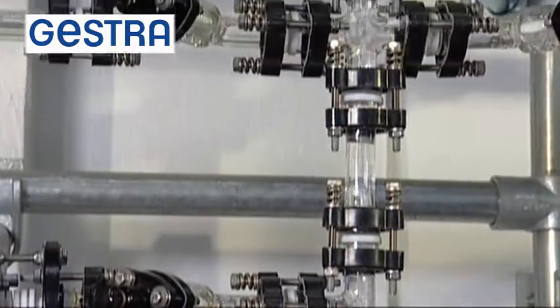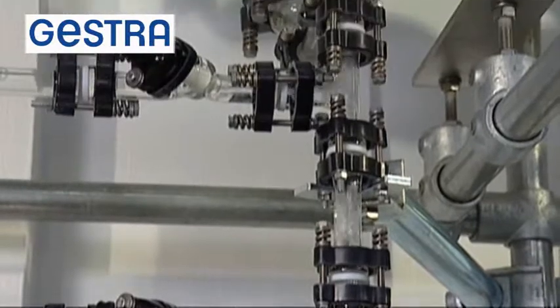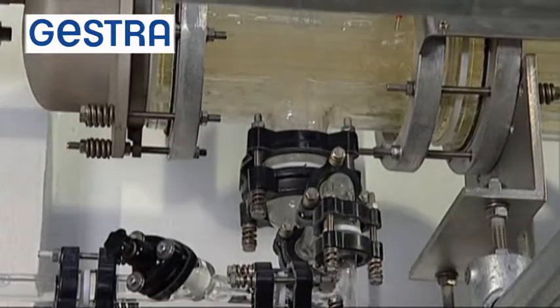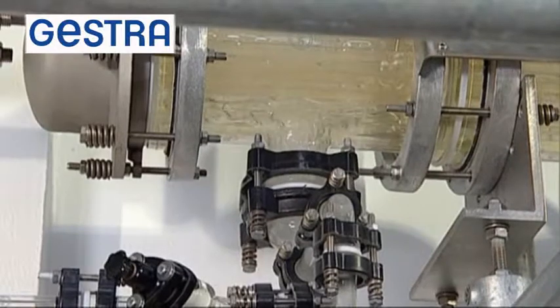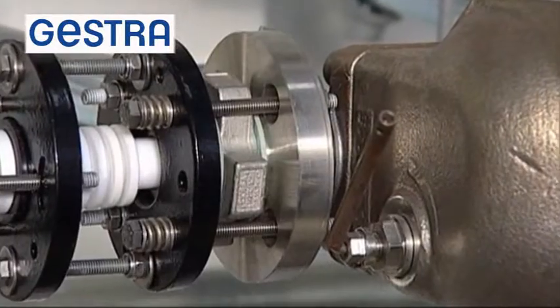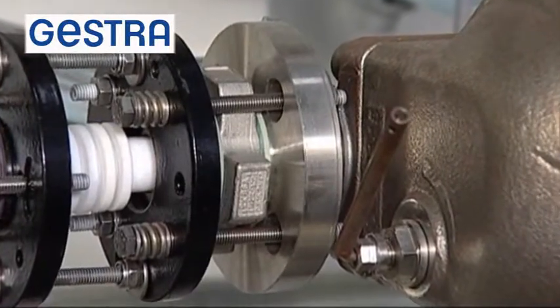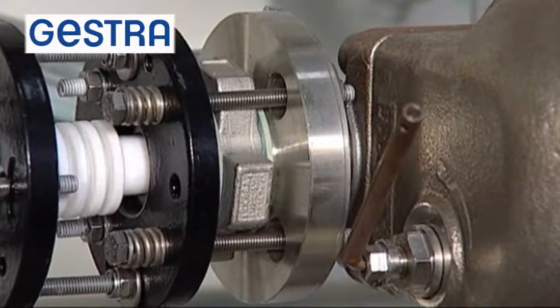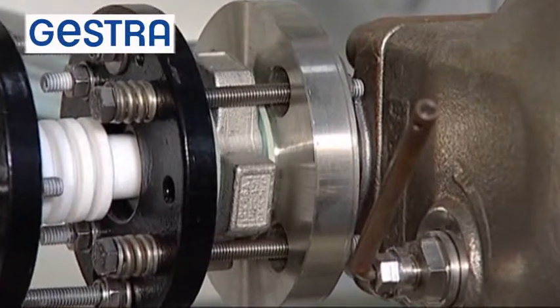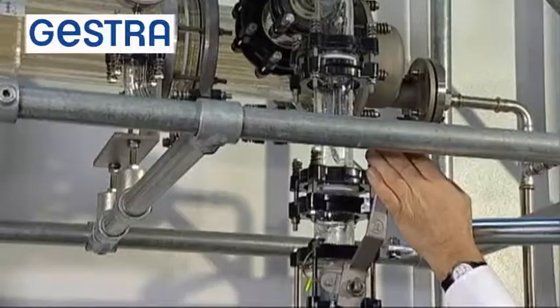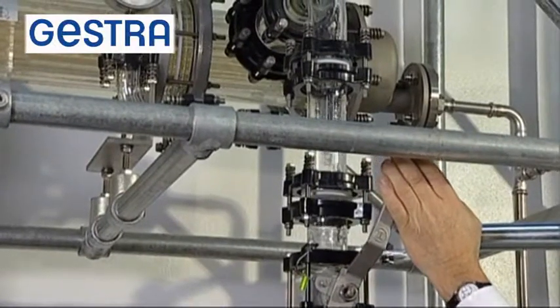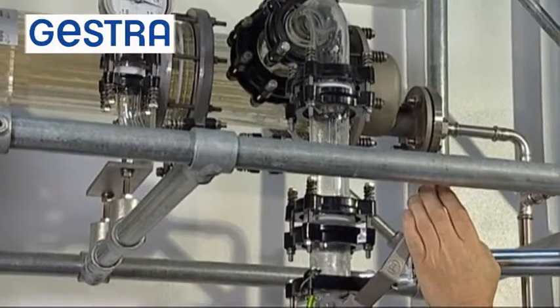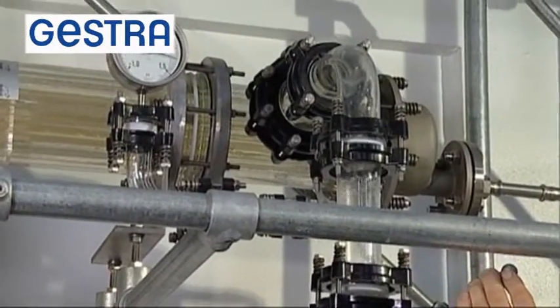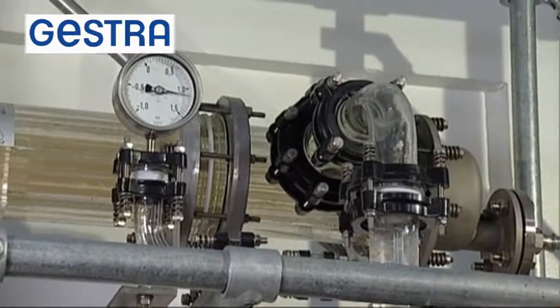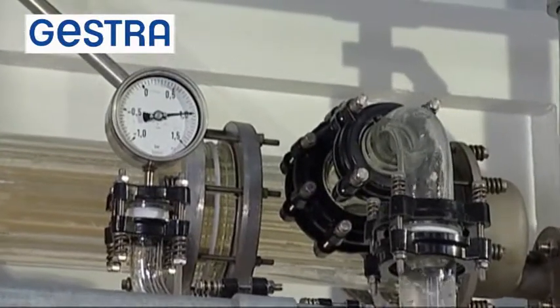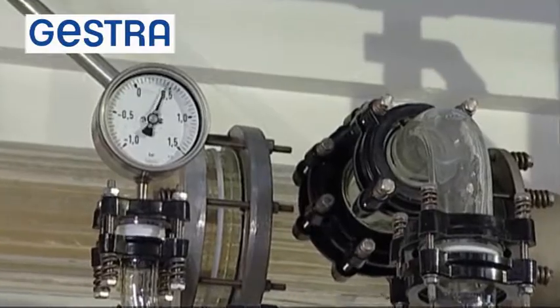When the steam control valve at the input of the heat exchanger closes, this can result in an extremely rapid pressure drop. A vacuum may be produced inside the heat exchanger. Condensate is then drawn through the steam trap back into the heat exchanger. This too is prevented by a non-return valve. In both of these cases, the GESTRA Disco non-return valve type RK has proven to be most effective. Just how rapidly the pressure in a heat exchanger can drop will now be demonstrated by closing the ball valve at the steam inlet of the heat exchanger. By watching the pressure gauge at the same time, we can see how the pressure drop occurs.